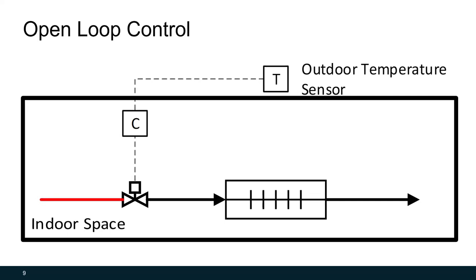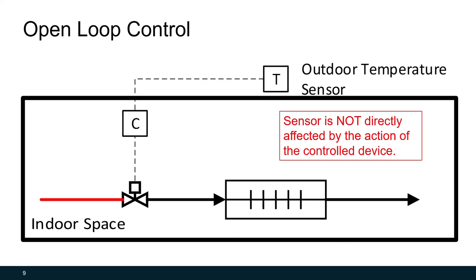This is an example of open loop control. Here we're heating a space with a hot water heat exchanger, but the temperature sensor has been moved outside of the building — it's measuring the outdoor temperature, not directly measuring our controlled variable, which is indoor space temperature. We really want the indoor space to be warm, not the outside. This is an open loop. It has its place, but it's not usually recommended because you're not directly measuring the variable.